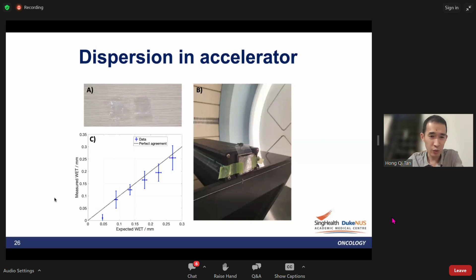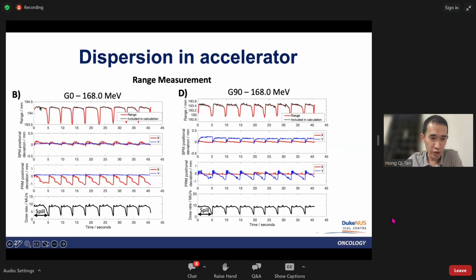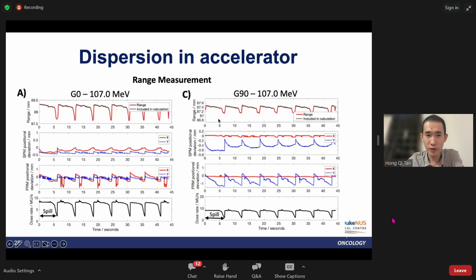These are some of our results. At 168.0 MeV, you can see that the range across the spill slightly dropped and is reproducible across all the different spills. When you go to gantry 3 90, the range shows similar measurements. If you look at the SPM and PRM positional deviations, you can see the drift. In gantry 3 0 degrees, the drift is in the X direction, whereas in gantry 3 90, it's in the Y direction due to precession of the phase space. At 107 MeV, we see a more prominent range drop for both gantries.